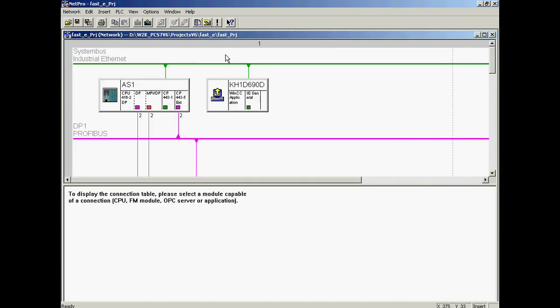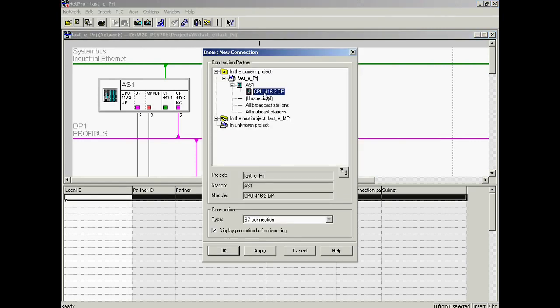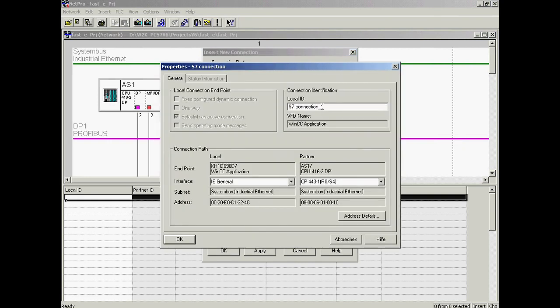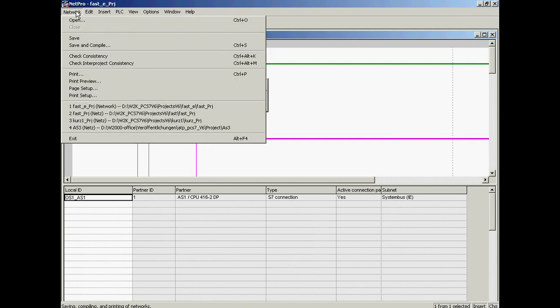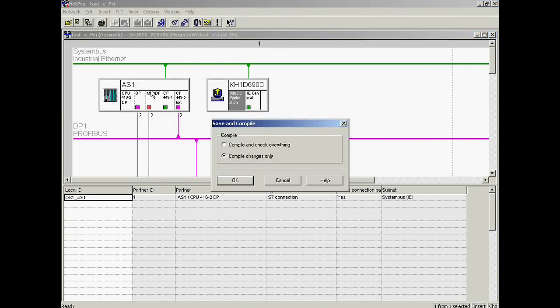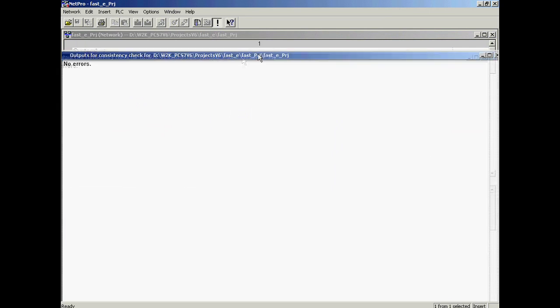In order to define the named connection, the WinCC application is first selected in the SIMATIC station. All existing connections are displayed in the table. A new connection is created by double-clicking on an empty cell — this is the CPU to which we want to define the connection. In the properties dialog, the name of the connection is changed to OS1_AS1. No further information is required. Now the changes must be saved and compiled. The compilation has been carried out without errors.